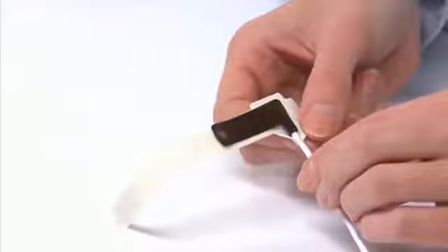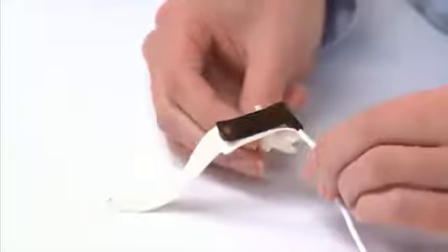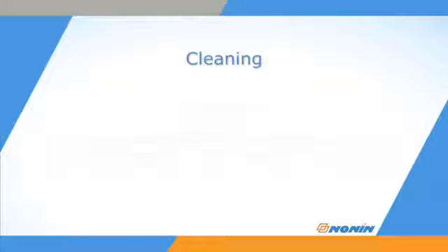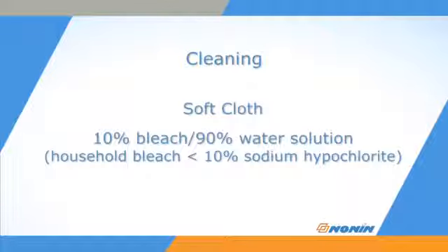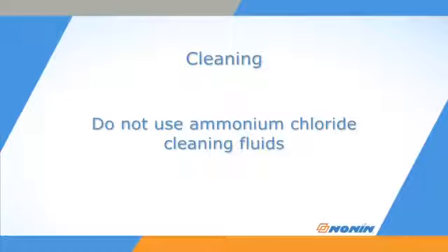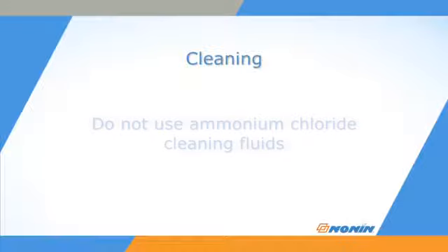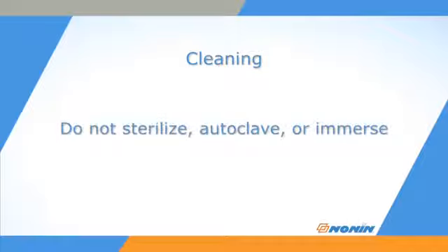Remove the Flex sensor from the FlexiWrap and discard the wrap. The Flex sensor can be cleaned for use with a different patient. To clean, you can wipe all patient contact surfaces of the sensor with a soft cloth dampened with a 10% bleach solution. Do not use caustic or ammonium chloride-based cleaners, which may damage the sensor elements. Do not sterilize, autoclave, or immerse the sensor in liquid of any kind.